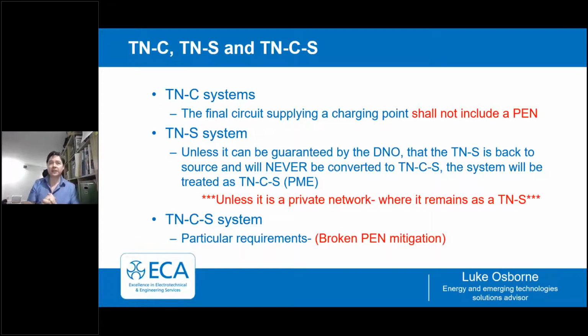But when it's a TNCS PME type system, there are particular requirements, and this is solely to address the issue of broken PENs. There's a minor number of instances out there, cited roughly one a day, of broken PENs. So this is where the earthing and the neutral in the connections between the supply and the building may become broken. So this is a lot of onerous activity to protect against something which is a minor incident, which is deemed as tolerable by the HSE, and so we are where we are with that.